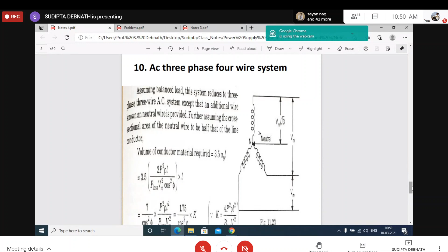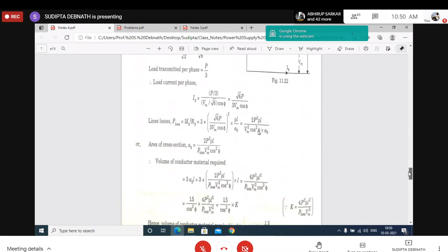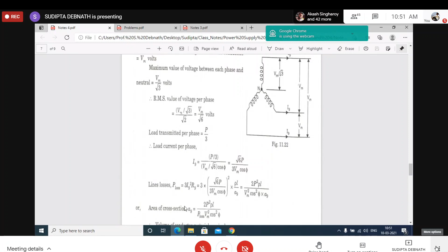Now this is all about AC three phase three-wire system. What is the difference in AC three phase four-wire system? You know, in AC three phase four-wire system also under balanced condition there is no current in the neutral. So up to this point, the calculation of power loss will be the same as that of AC three phase three-wire system, because everything will remain the same. Only one extra conductor is available, though it is not carrying any current under balanced condition. So for power loss, you have to write 3I square R only. You need not consider the neutral conductor. So up to this point, everything will remain the same.